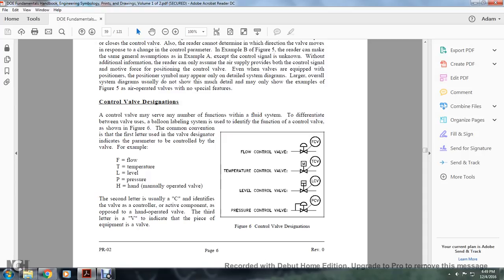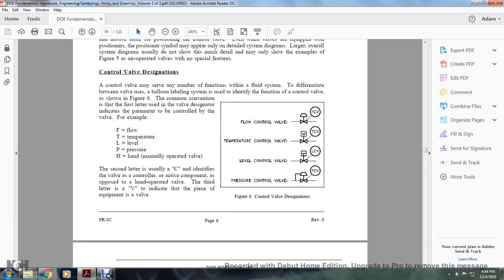Control Valve Designation: the control valve may serve a number of functions in a fluid system. A balloon-and-labeling system identifies the function of the control valve, as shown in Figure 6. The common convention: the first letter in the valve designator indicates the parameter to be controlled — F for flow, T for temperature, L for level, P for pressure, H for hand (manually operated valve). The second letter, C, identifies the valve as controller-actuated. The third letter, V, indicates the piece of equipment is a valve. So FCV is a flow control valve, TCV is a temperature control valve, LCV is a level control valve, and PCV is a pressure control valve.